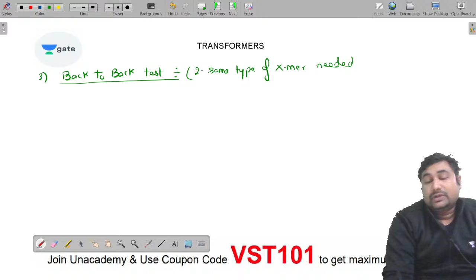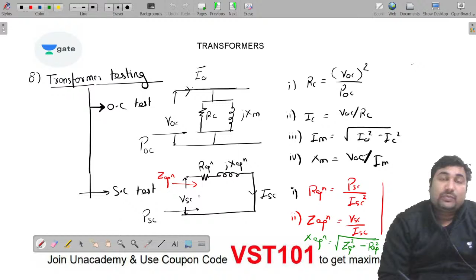Come to the fourth part, about the wattmeter. For OC test we use a low power factor wattmeter. However, for SC test we use a normal power factor wattmeter, because the power factor during the SC test of the transformer is in the range of 0.5 to 0.6.